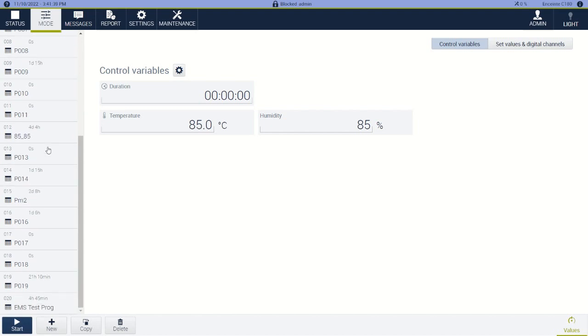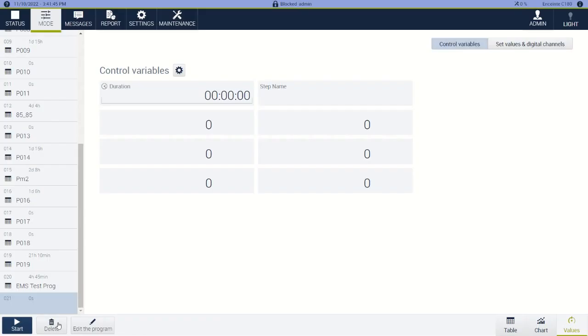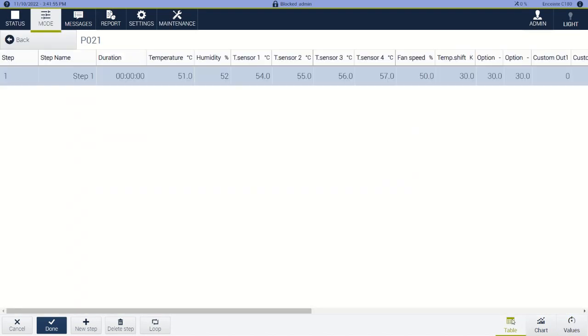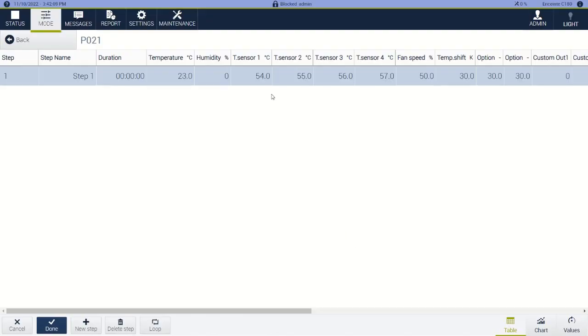So here let's go to a new program. We'll click new. This here is the standard editing mode, but I would recommend editing in table mode — it's more similar to Microsoft Excel and it will be easier to read. So for duration, let's say we want to start at ambient, so we'll do 23°C and 0% humidity. I'm going to leave all of these as is, because again this is a demo controller.